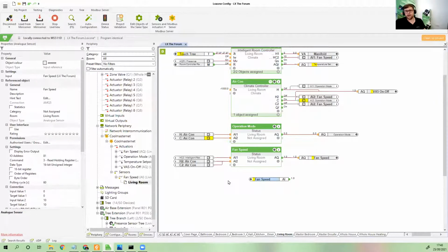However, if you've got a proper Loxone system with a touch switch or a touch pure, why would you? Because that's going to be more accurate. Before we had the demo case here with the touch switch in, I was reading the temperature from the AC unit, and it was always out by about 2 degrees. So hence why I'm reading it from a touch switch. But Nick, to be honest, I just don't really see the need to read the registers. If it works, it works. Keep it simple, stupid.